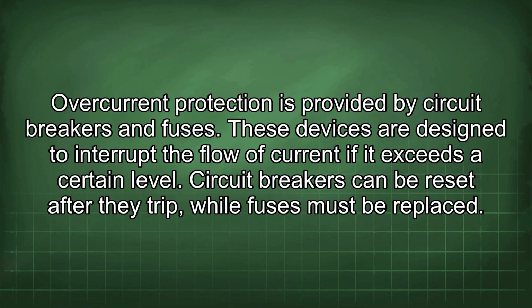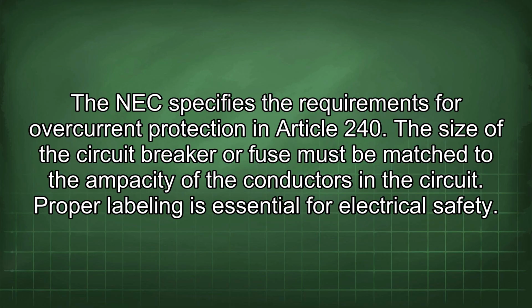Overcurrent protection is provided by circuit breakers and fuses. These devices are designed to interrupt the flow of current if it exceeds a certain level. Circuit breakers can be reset after they trip, while fuses must be replaced. The NEC specifies the requirements for overcurrent protection in Article 240. The size of the circuit breaker or fuse must be matched to the ampacity of the conductors in the circuit.